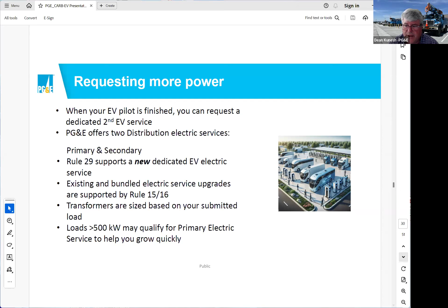Quite often I get asked, well, if I want a primary electric service, how much load do I need? So to qualify for a primary electric service with PG&E, your load has to be above 500 kW. It's rather substantial for that type of load, above 500 kW, okay.